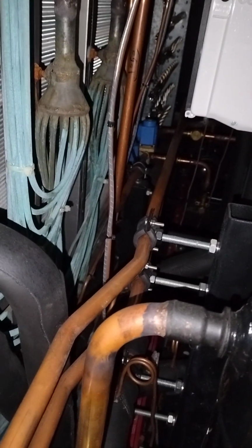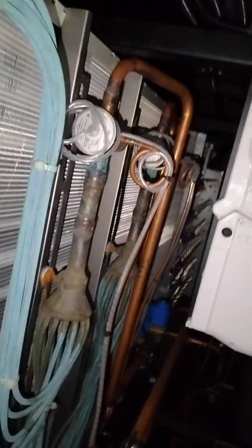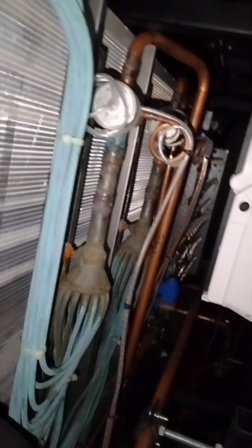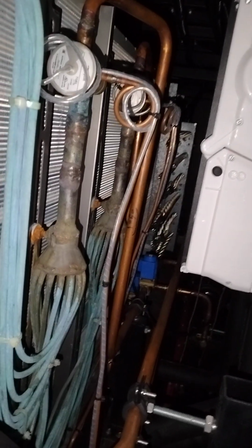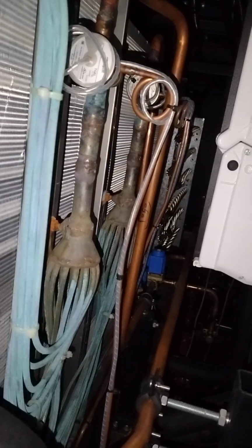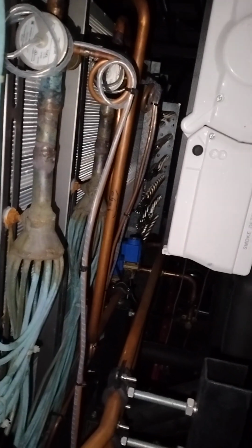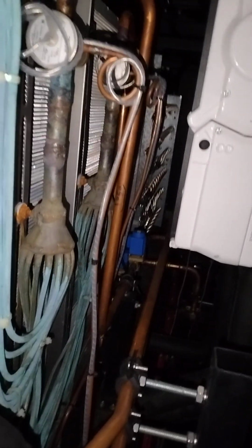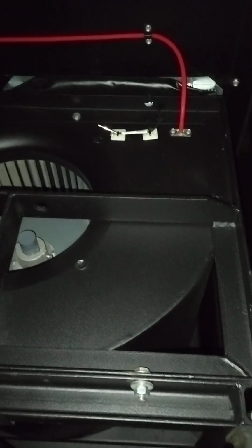And then it goes through these liquid lines, going up to the expansion valve. That's the distributor, and the distributor distributes through that coil. It's a little bit large coil. Maybe you can see there we also have reheater coils, these kind of heater cores at the back, that's aluminum-like. And then that is the blower motor. We have two blowers here, with square housings, and then the top discharge from that side. That is a supply temperature sensor.